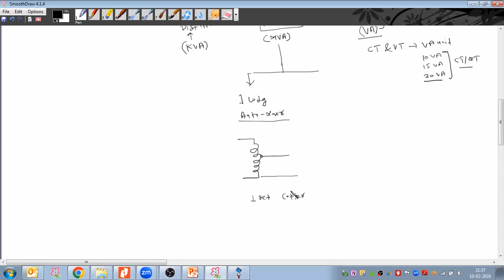Again, this power transformer we can divide into three parts. It could be a one winding transformer, called an auto transformer. It means in this particular transformer we do not have two windings, we have a single winding, and to make the LV voltage we take tappings from the winding. So what is the advantage? In a two winding transformer we have two sets of copper winding, but in case of an auto transformer we have only one set of copper winding and core. So I am able to reduce the cost of the transformer drastically, right?